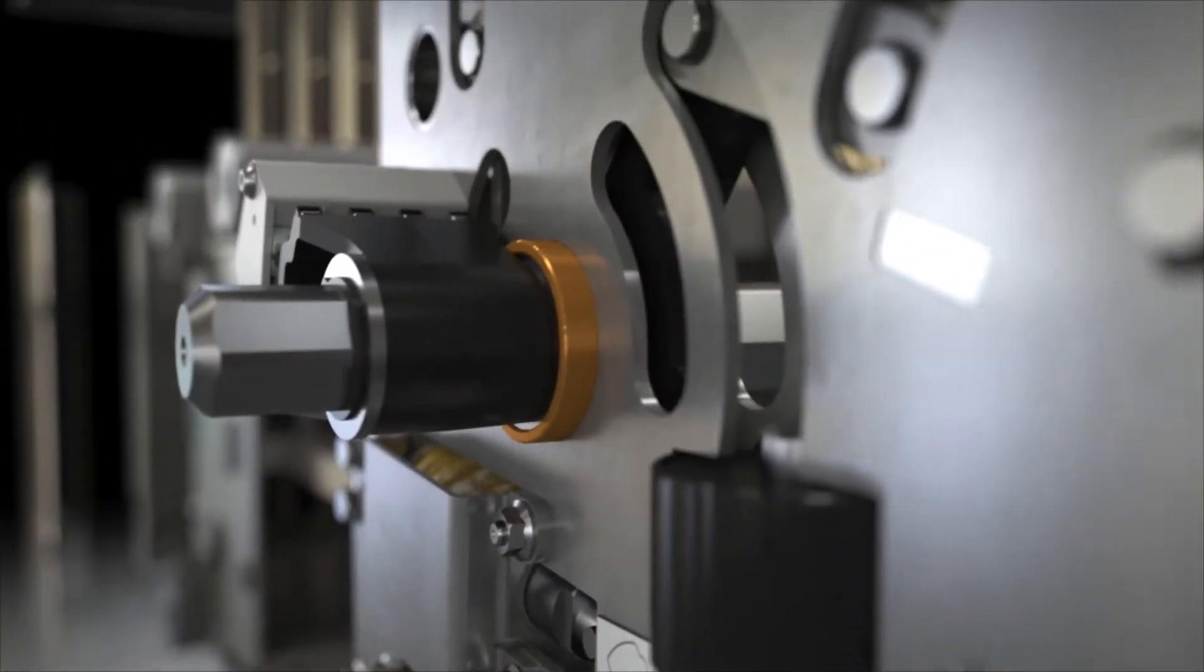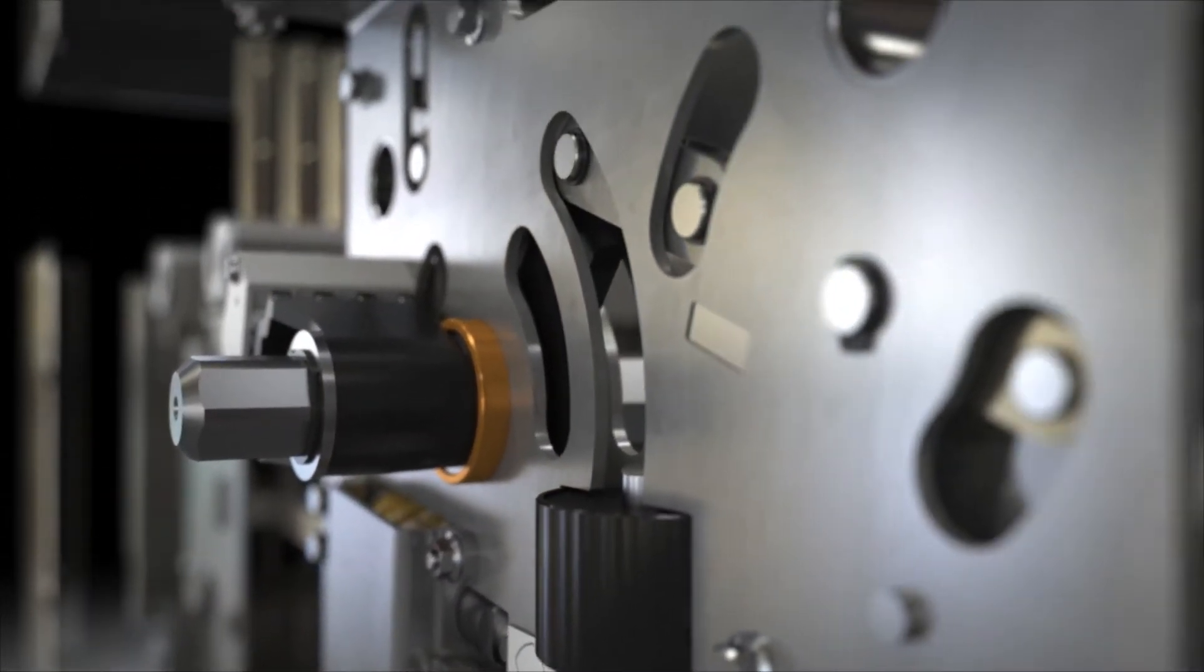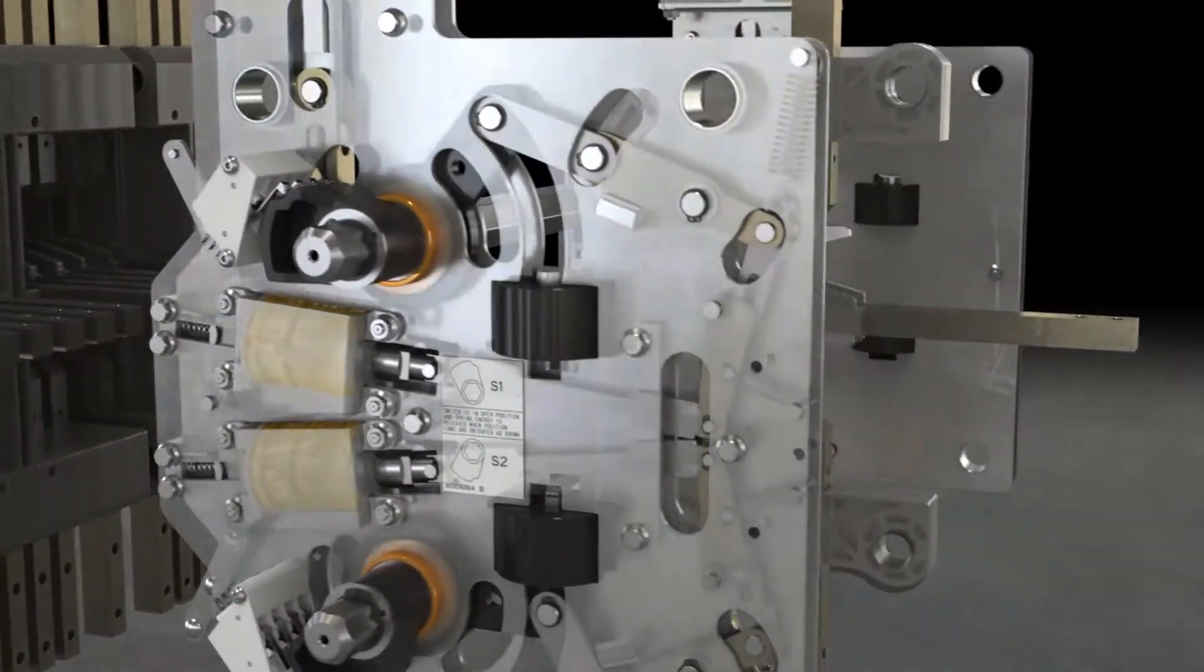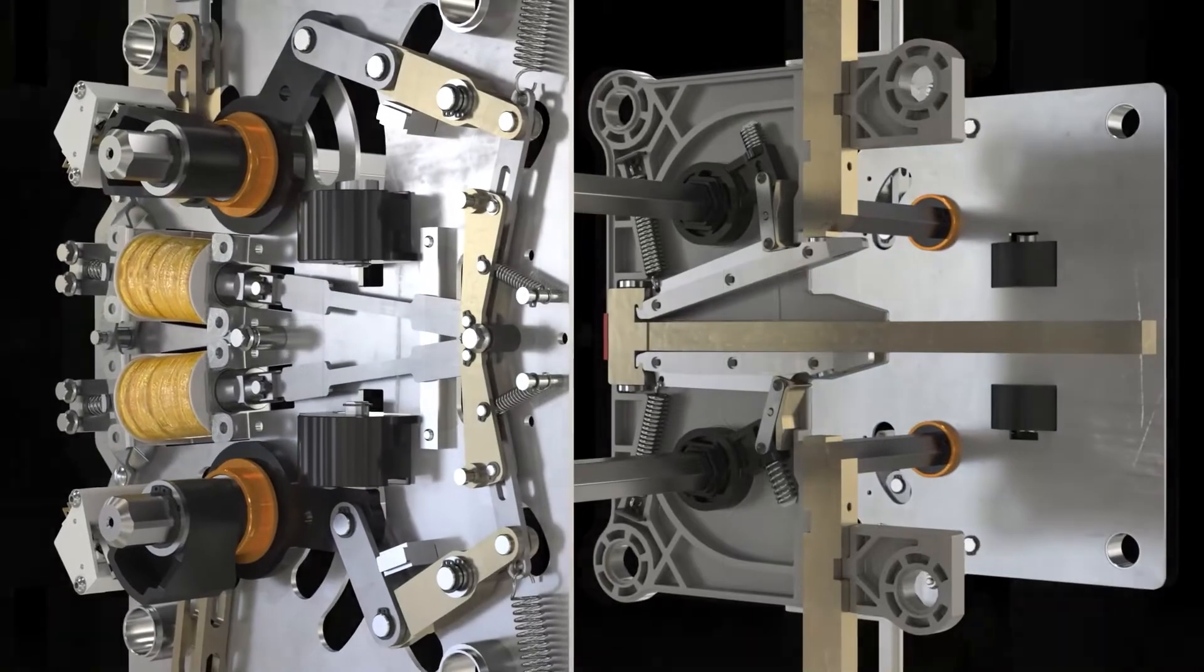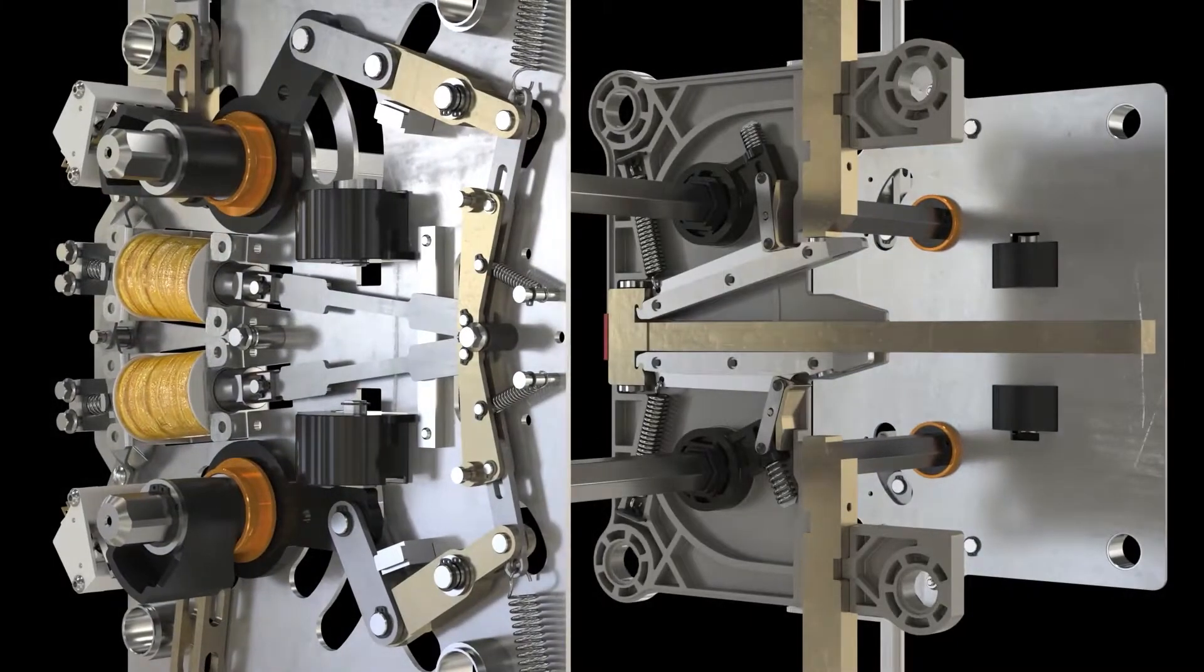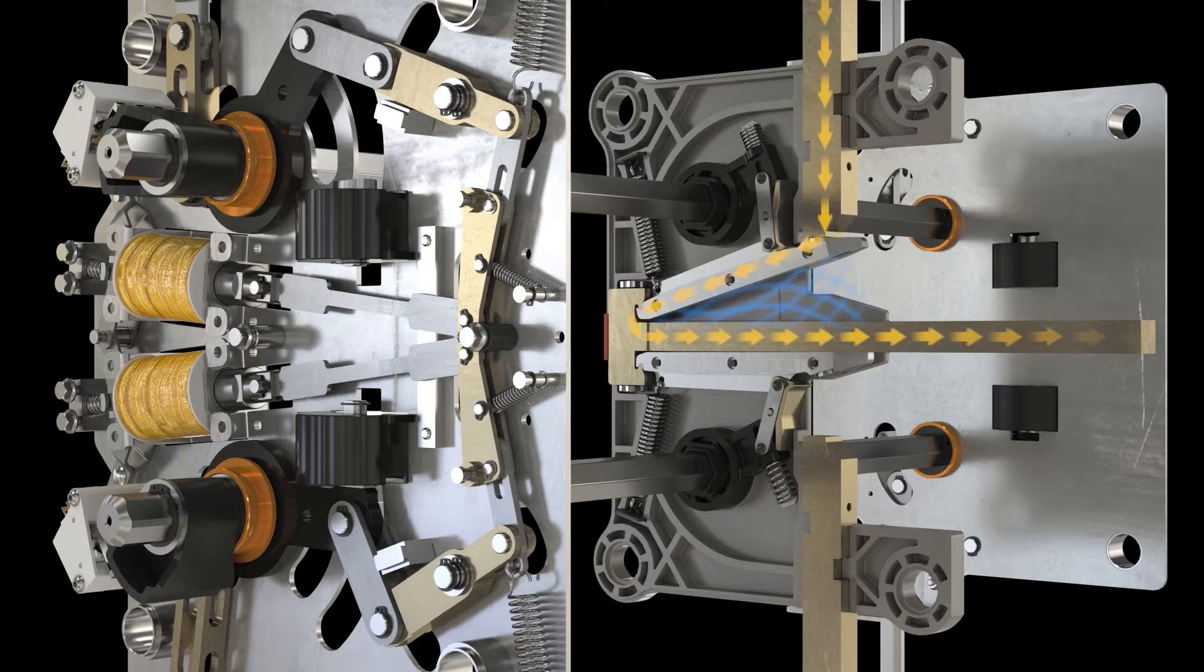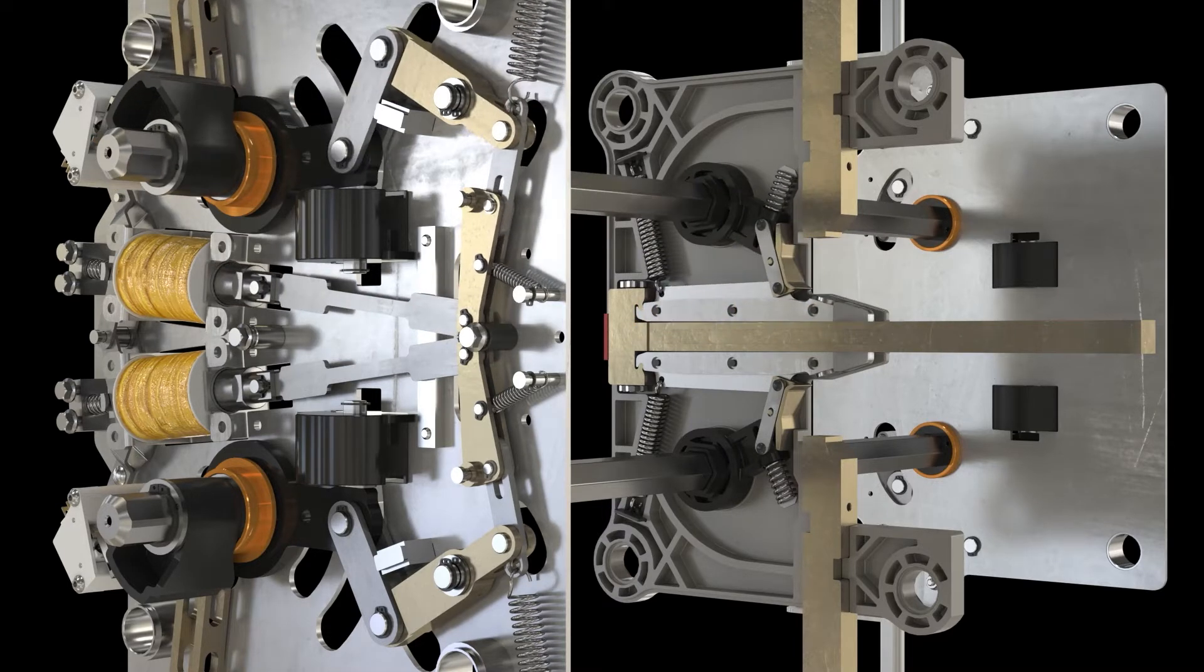This patented blow-on design allows for high survivability in extreme fault current conditions. The higher the fault, the stronger the electromagnetic force that keeps the switch contacts closed, which delivers the superior short-circuit withstand and short-time ratings.